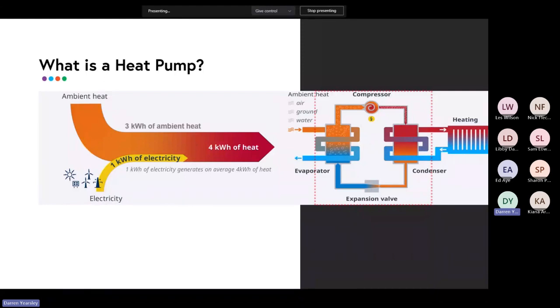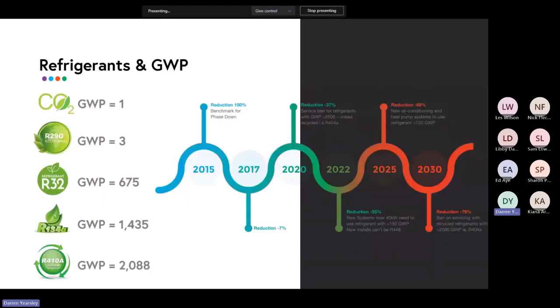So just to summarize, an air-to-water heat pump runs at what we call a COP, coefficient of performance, and it's always stated as a ratio. Depending on the application, it'll be 3:1, 4:1, 5:1 is not uncommon. What that means is the input is the 1 kilowatt and the output is the other number, so 4 kilowatts, for instance. Something which is changing continuously in this space is the refrigerants. So I'll just give you a general overview of the common refrigerants available in the market today.